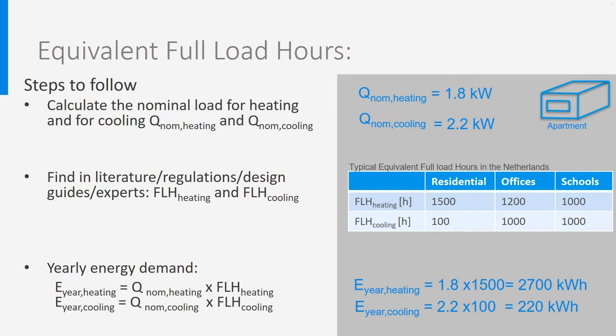Let's study further how it works in practice. There are three steps — on the left the steps, on the right the example. As an example, we take again the small apartment we studied in former lectures. The first step is to calculate the nominal powers for space heating and space cooling. From the former lecture, we found for this apartment a nominal heating power of 1.8 kilowatt, and for the cooling it was 2.2 kilowatt.